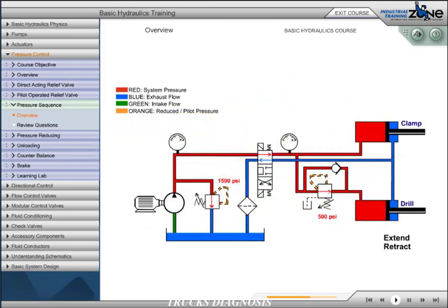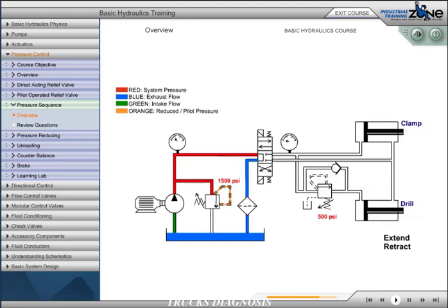This will ensure that the drill will not extend before we have reached 500 PSI on the clamp cylinder. Notice that once the drill cylinder has extended, pressure will continue to rise to the system relief setting of 1500 PSI.